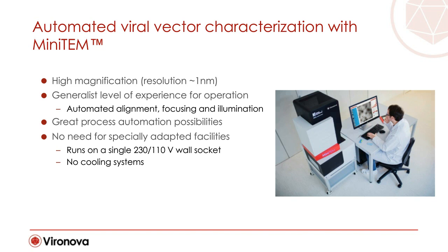The instrument can be placed in a standard laboratory setting with no extra requirements of mechanical or electromagnetic interferences, which is usually the case when acquiring a full-sized electron microscope. Installation and commissioning takes a few days.